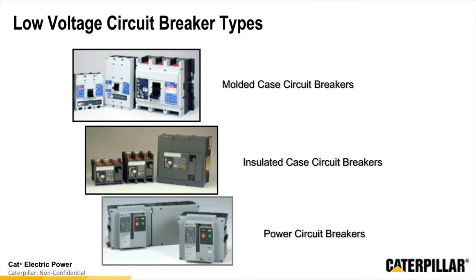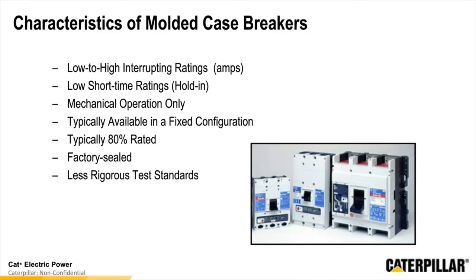So we've talked about the protective relays and the protection that we have associated there. Now let's start looking at our circuit breakers in our system. There's primarily 3 different types of circuit breakers that we're going to talk about. There are molded case circuit breakers, there are insulated case circuit breakers, and there are power circuit breakers. So the first breaker we're looking at is the molded case breaker. This typically has low to high interrupt ratings. So these are breakers that you may find, like I talked about in the beginning, in your home, all the way up to something that would be throughout your system.